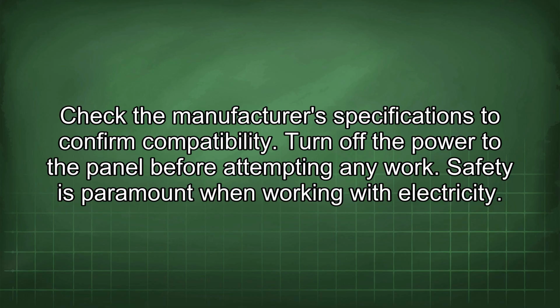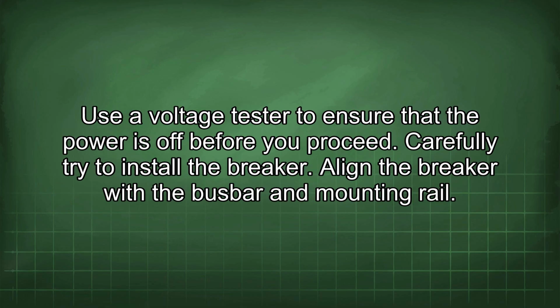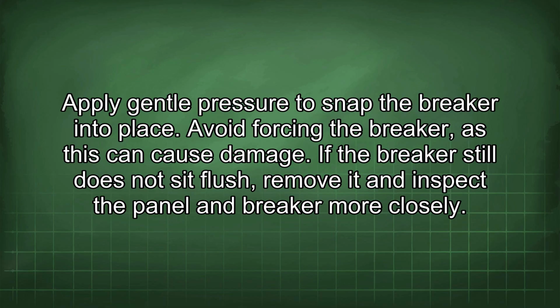Safety is paramount when working with electricity. Use a voltage tester to ensure that the power is off before you proceed. Carefully try to install the breaker. Align the breaker with the busbar and mounting rail. Apply gentle pressure to snap the breaker into place. Avoid forcing the breaker, as this can cause damage.